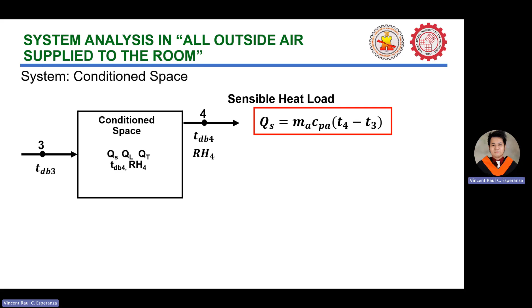Ayan. So, if i-graph natin ito sa isang psychrometric chart, itong buong system na ito. So, this is the psychrometric diagram. At point 1, this is the outside air at a given dry bulb temperature and specific humidity or RH. Then this is further cooled and dehumidified until it reaches its saturation point, which is at point 2, which represents RH equal to 100%, with a dry bulb temperature at point 2. So nagkaroon ng sensible cooling and further cooling by means of dehumidifying. Kaya naging cooling and dehumidifying process.